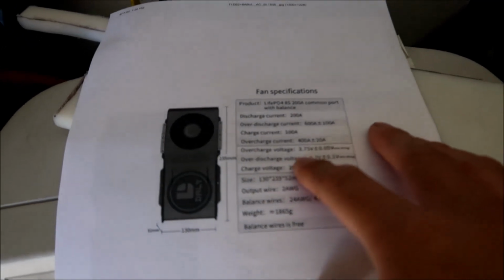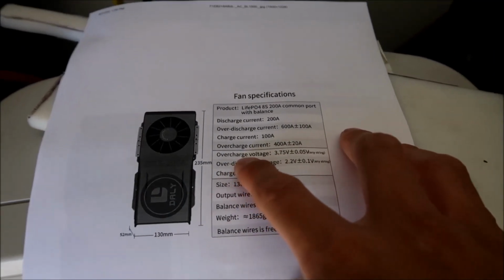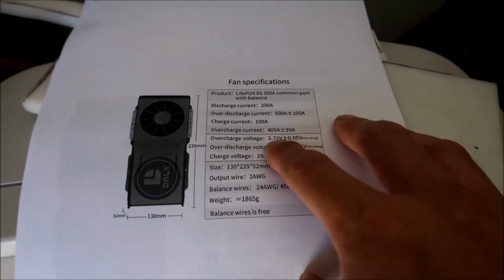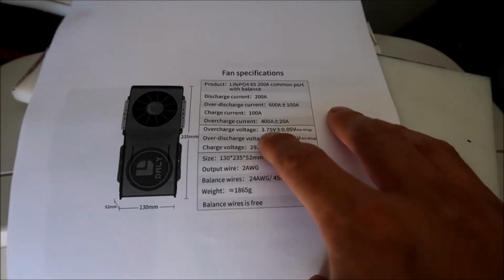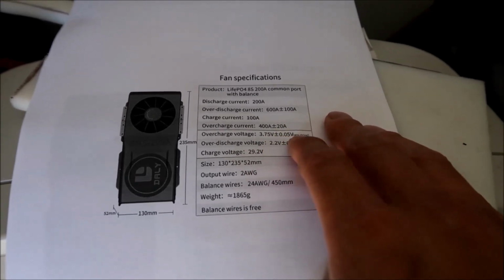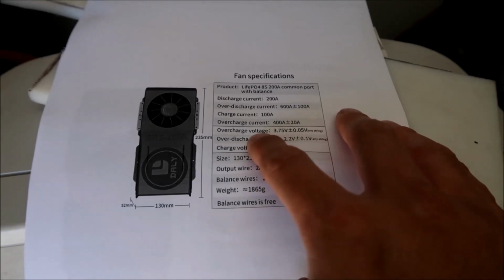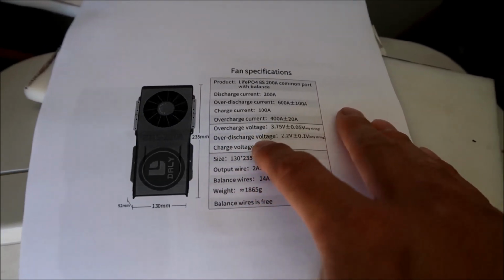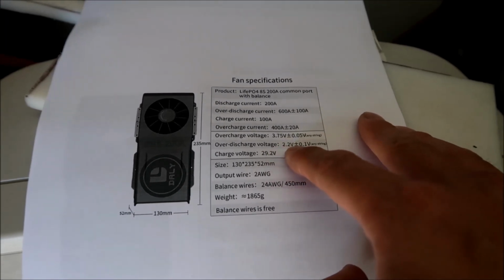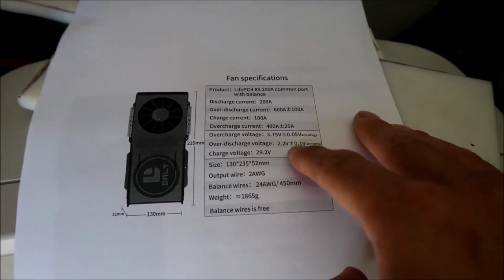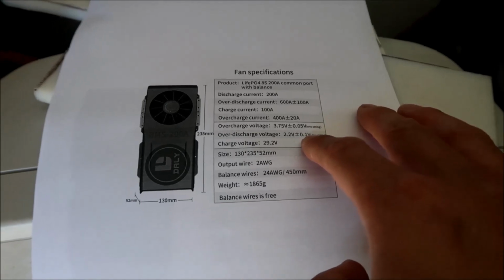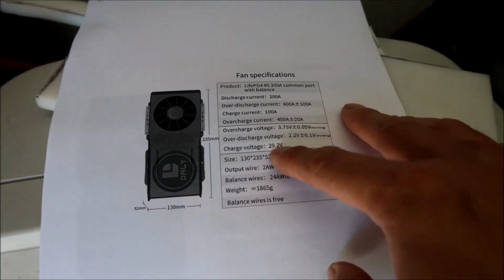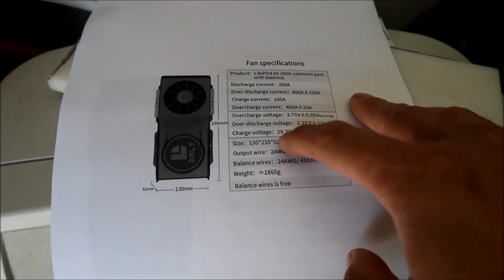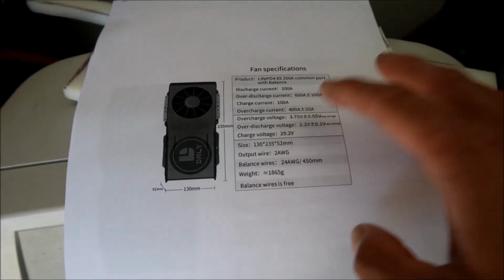So this is the overcharge voltage. If it sees any of the cells go over 3.75 plus or minus 0.05 volts, it will disconnect the BMS. And if any cell goes below 2.2 volts, plus or minus 0.1 volts, it'll disconnect. The charge voltage is 29.2, like I mentioned, so when it hits 29.2 volts it should stop charging.